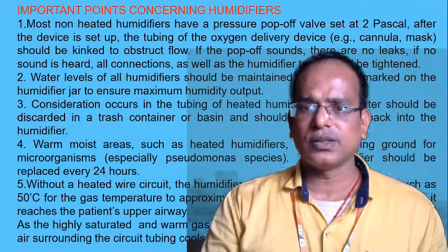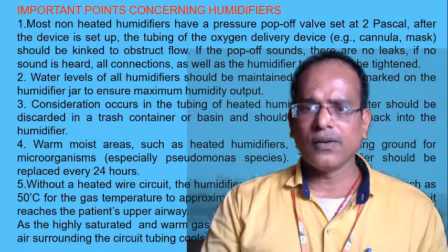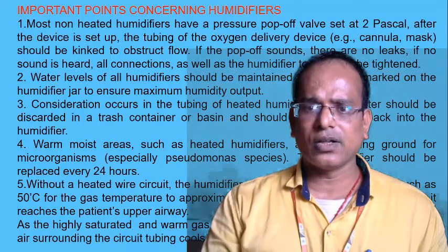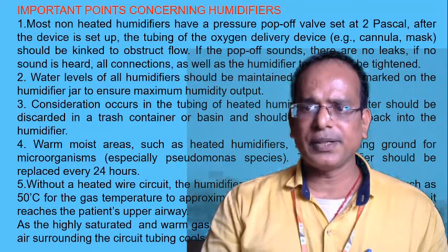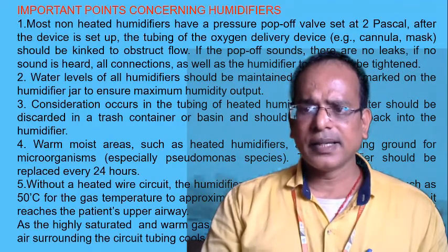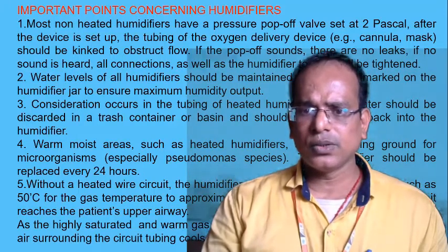Third one, condensation occurs in the tubing of a heated humidifier. This water should be discarded in a trash container or basin and should never be put back into the humidifier. Fourth one, warm moist areas such as heated humidifiers are a breeding ground for microorganisms, especially Pseudomonas species. The humidifiers should be replaced every 24 hours.